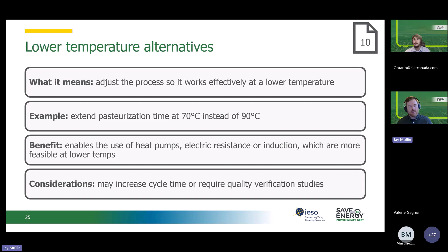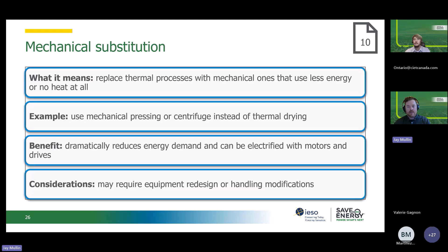Another option is mechanical substitution, so replacing thermal processes with mechanical ones that use less heat energy or no heat energy at all. One example could be mechanical pressing or a centrifuge instead of thermal drying, and this can dramatically reduce the heat energy demand and can be electrified with motors, drives, might require equipment redesign, handling modifications. It also might not fully eliminate the need for heat, but can reduce how much is needed to reduce the impact on those operating costs related to heating.